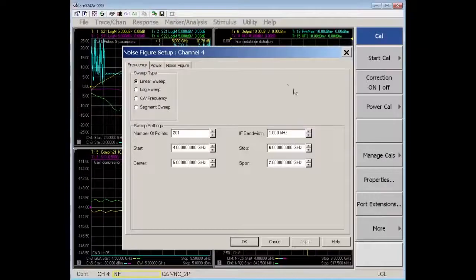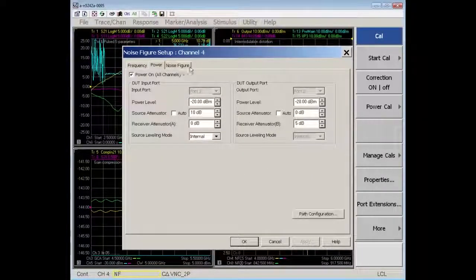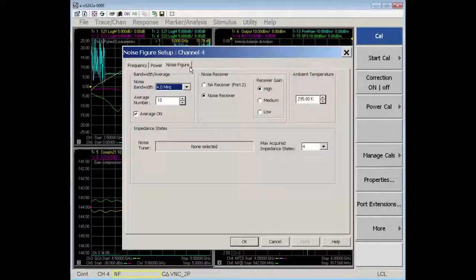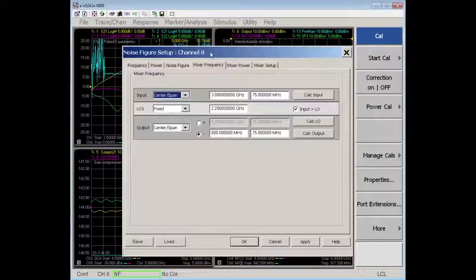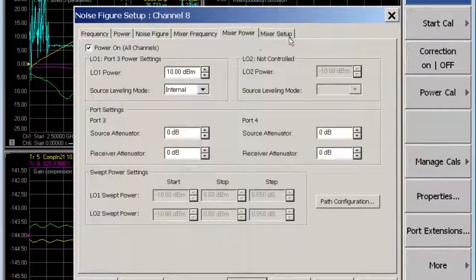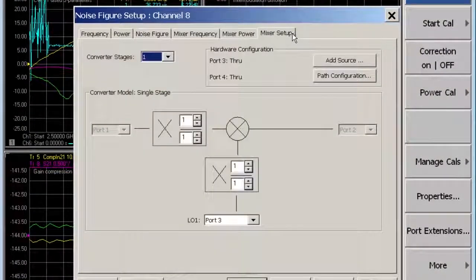Setting up noise figure measurements on the PNA-X is easy using a tab dialog box where all of the necessary setup information is entered. When measuring converters, three additional tabs are used to define the mixing plan and local oscillator setup.